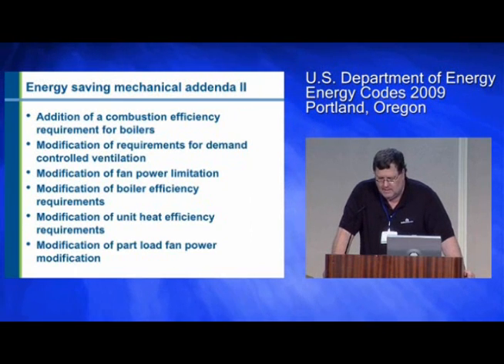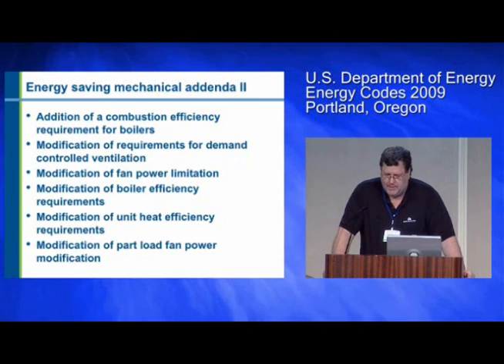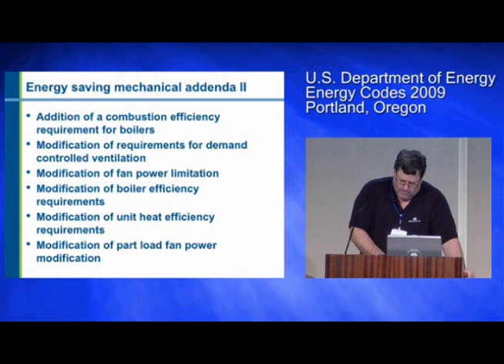Moving on to some of the other changes that are going to show up in 90.1-2007, there's a new combustion efficiency requirement for boilers. There are new requirements for demand-controlled ventilation. There's a modification of the existing fan power limitation. That's the requirement that tells you how much power you're allowed to use for your fan system, depending on how big the system is. There's modification of the boiler efficiency requirements, modification of unit heater efficiency requirements, and some changes in the part load fan power requirements as well.